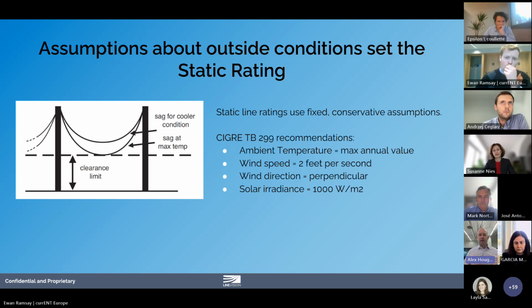And so you might think about, well, this doesn't sound all that complicated. If we understand the temperature, we should be able to understand how much power we can move. And that's exactly right. But the challenge is, and Brian will start touching on this and how this is actually deployed, transmission assets as a category are the least monitored, the least understood in real time of all assets that a utility might own. Because once a transmission line leaves a substation, virtually all transmission lines have no monitoring. And so that is exactly why operators have to use these assumptions to load their lines. And of course, they need to be very conservative, because if you don't understand what's happening out there in the real world, you have to always assume that it's the worst case scenario.